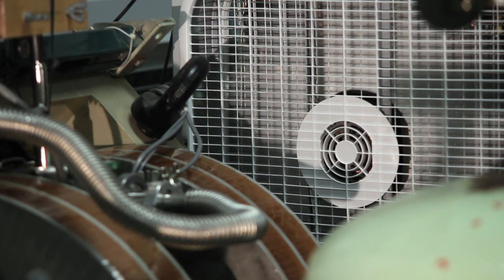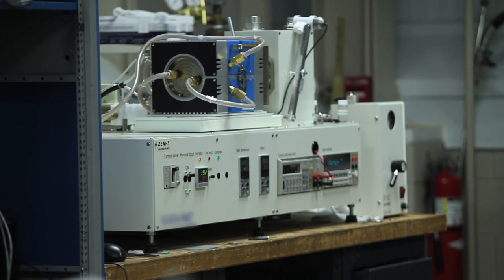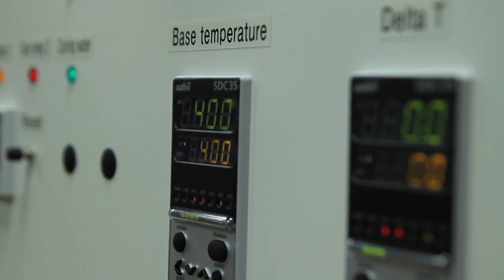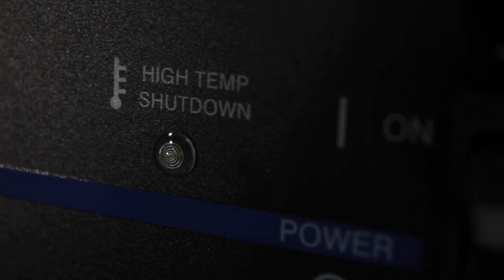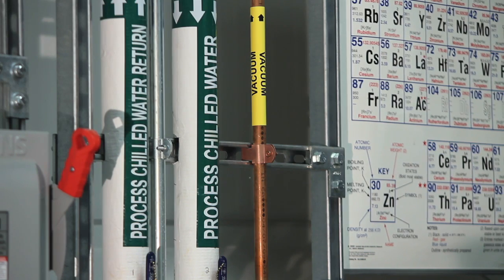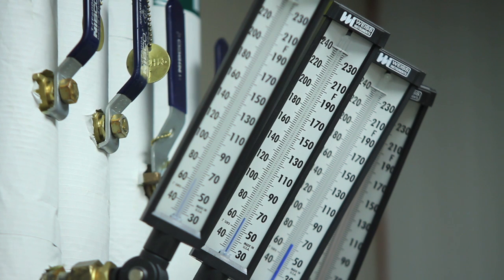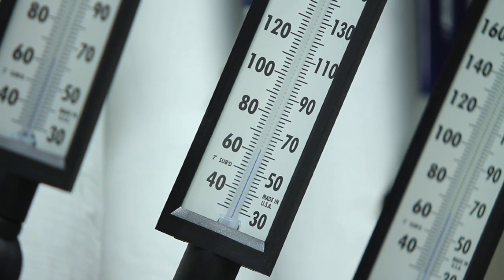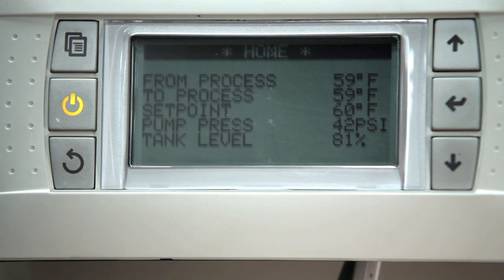Our laboratory generally deals with what we call electronic materials. We're interested in synthesizing new materials and characterizing their thermal, magnetic, and electronic properties for potential applications. Much of our equipment needs active cooling because it's operated at high temperatures, such as the furnaces, or at very high power levels. One power supply we have operates at about 10 kilowatts of electrical power and produces a lot of heat, so that needs active cooling.